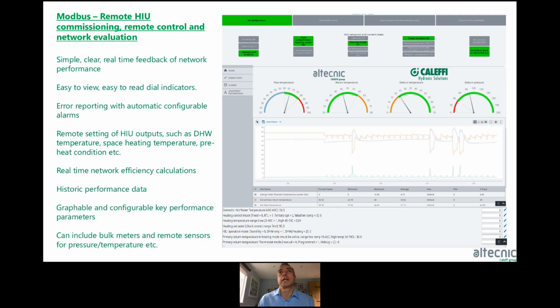Then it tells you a little bit here about what the HIU is doing, what mode it's in. If it's in here, it's green, showing heating and domestic hot water, but you could have hot water only or standby. And then you have some of the more advanced features that we have on our SAT-K range, where you have return temperature limitation, you can have weather compensation, pasteurization included. There's all kinds of things. Primary flow rate limitation is a real good one, but it'll tell you what mode that's in.